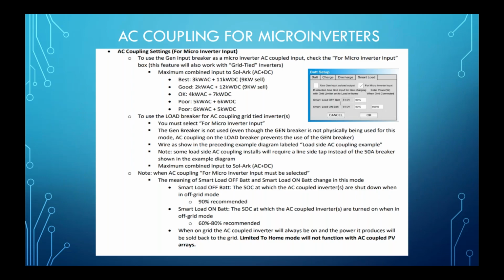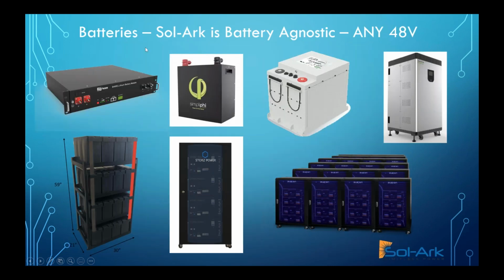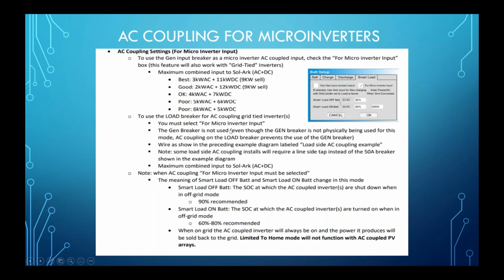This is a note about if you are going to AC couple and there are micro inverters. There are a couple of different ways to do it. You can use the generator input breaker as the micro inverter input, or the AC coupled input. Or you can use the load breaker. Either way, you're going to want to go into the battery setup menu, and I apologize, but we're going to see all the menus moving forward.